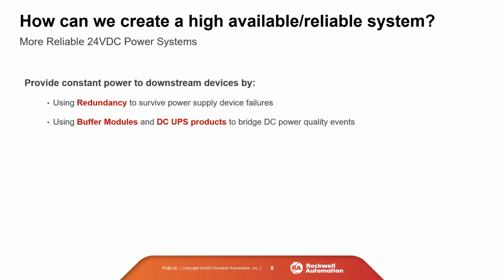So how can we create a highly available, reliable system? Well, we can use redundancy to survive if the actual power supply device fails, or we can use buffer modules and UPS products to bridge DC power quality events. So think like that motor starting up.